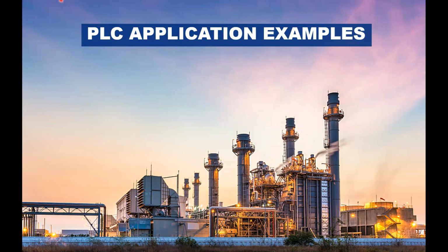Okay, if I understand well, you are asking about our hardware and the timestamp, the accuracy of our digital inputs and digital outputs. Am I right? I'm talking about analog inputs, analog outputs, digital inputs, digital outputs, everything. And I'm also considering the fact that there are timing cycles as well. For example, the token passing mechanism. How do you pass and how fast? What's the frequency of token passing when it comes to your hardware? While you might have implemented a Modbus stack, you generally would not receive such limitations.